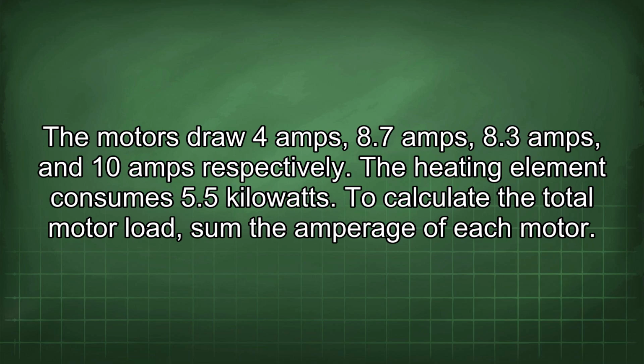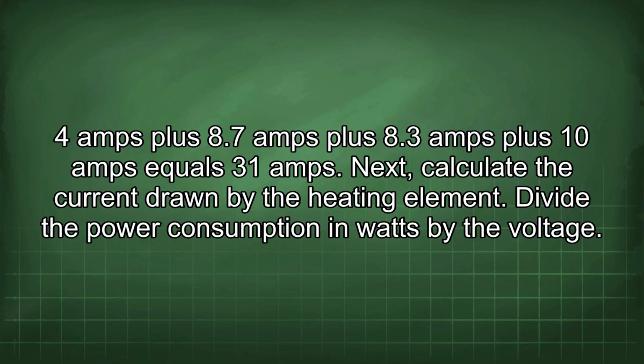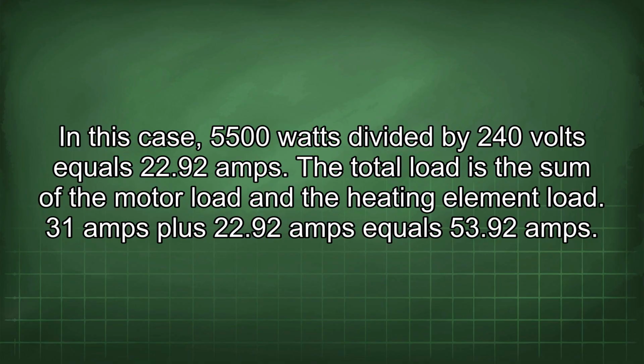To calculate the total motor load, sum the amperage of each motor. 4 amps plus 8.7 amps plus 8.3 amps plus 10 amps equals 31 amps. Next, calculate the current drawn by the heating element. Divide the power consumption in watts by the voltage. In this case, 5,500 watts divided by 240 volts equals 22.92 amps. The total load is the sum of the motor load and the heating element load. 31 amps plus 22.92 amps equals 53.92 amps.